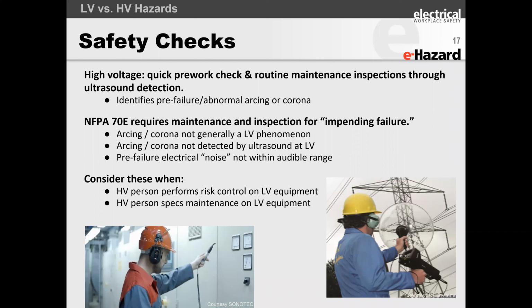Well, folks, at low voltage it is extremely quiet, extremely quiet. Even with ultrasonic sensors, sometimes they don't have enough resolution to be able to pick up impending failure. Generally at low voltage, you have a runaway, whereas at high voltage, you get corona forming, you get pitting, you get expansion of the corona region, and then you go into a breakdown. At low voltage, you go from hero to zero near immediately. I mean, it's a magnitude different compared to high voltage. So even our safety checks, listening for high voltage, does not work at low voltage, all right? Higher voltages, you're outdoors, you have sun, you have reflection of the surface heat.